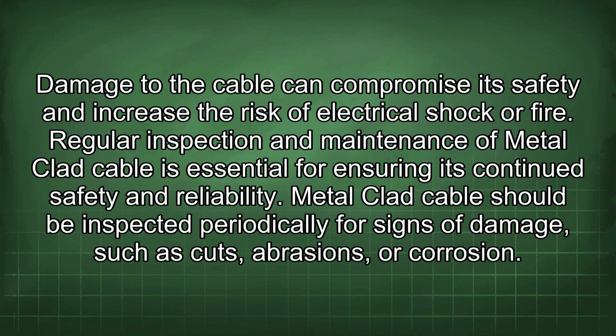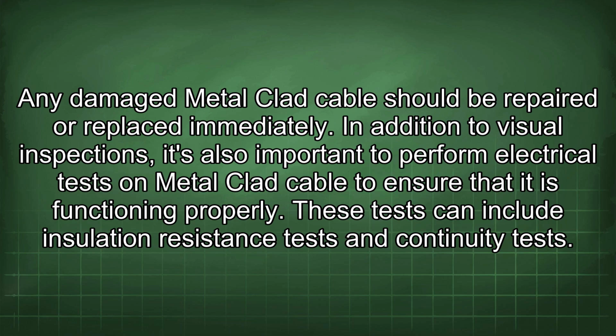Regular inspection and maintenance of metal-clad cable is essential for ensuring its continued safety and reliability. Metal-clad cable should be inspected periodically for signs of damage such as cuts, abrasions, or corrosion. Any damaged metal-clad cable should be repaired or replaced immediately. In addition to visual inspections, it's also important to perform electrical tests on metal-clad cable to ensure that it is functioning properly. These tests can include insulation resistance tests and continuity tests.